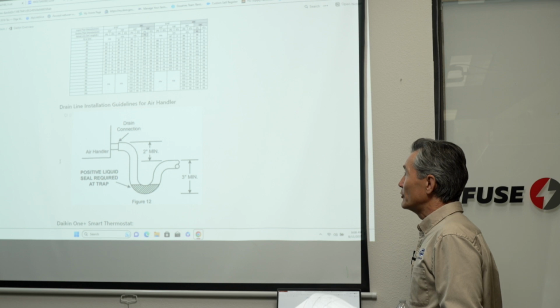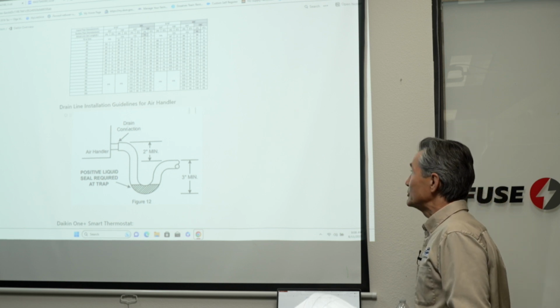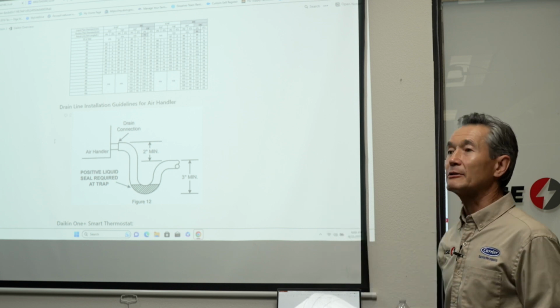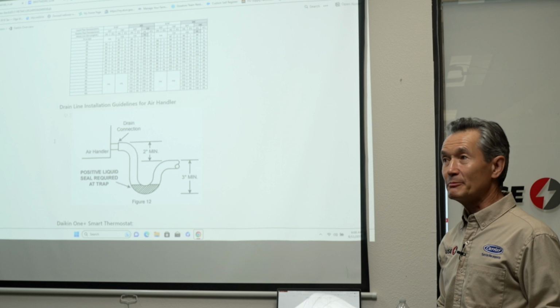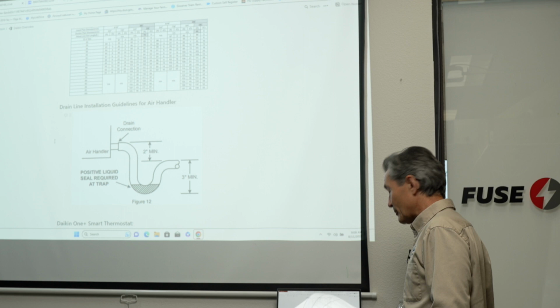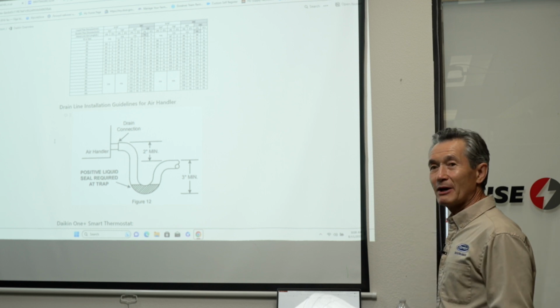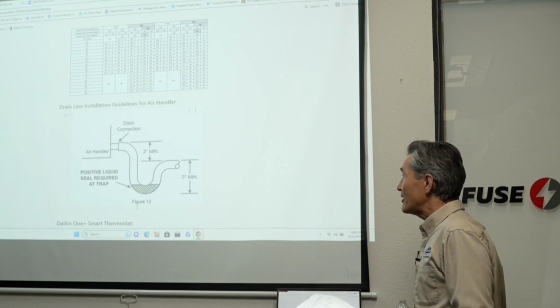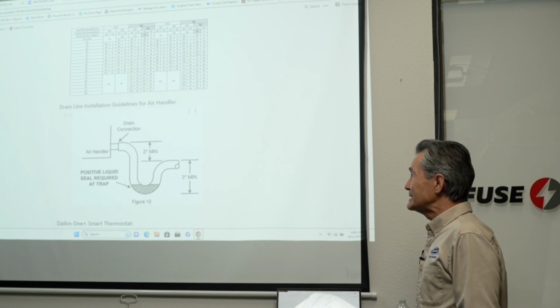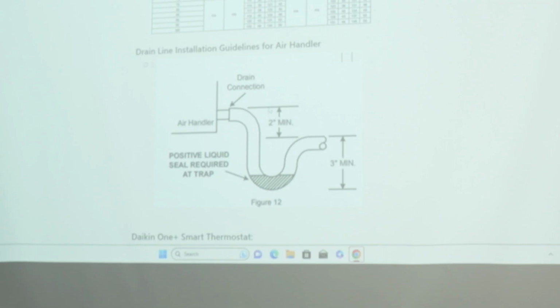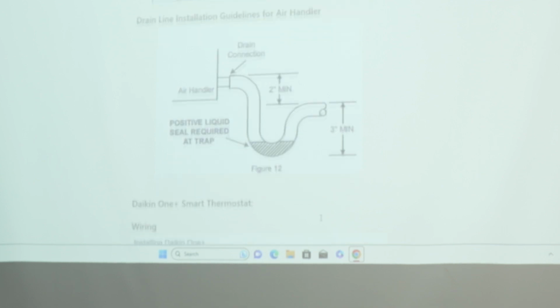Another important thing to remember during installation, especially with an air handler, is that it's negative pressure inside. The blower is located on top and the coil is below, so it's basically sucking the pressure. That's why, if a customer mentions a certain smell, it might be because you don't have the proper liquid trap sized properly - these sizes should be done correctly. Infinity, Carrier, and others say minimum 4 for new units. It's a very similar concept, so it has to be applied properly.